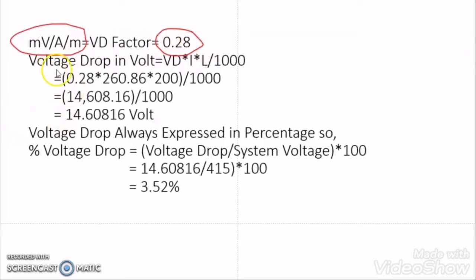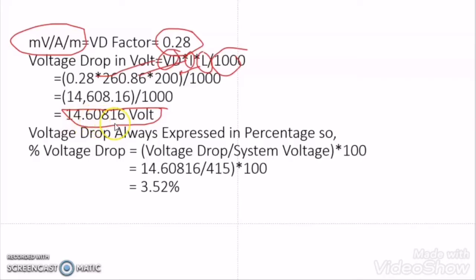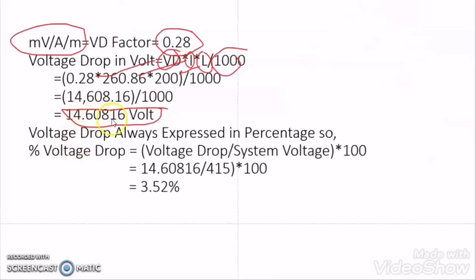Now we have all the information. Voltage drop in volts = VD factor × load current × length of cable / 1000. VD factor is 0.28, I is 260.86 A, and the length of the cable from the question is 200 meters, divided by 1000. When we calculate, we get a voltage drop of 14.60 V. This means if the voltage at the panel end is 415 V, then the voltage at the motor end will be 415 − 14.6 = 400.4 V.